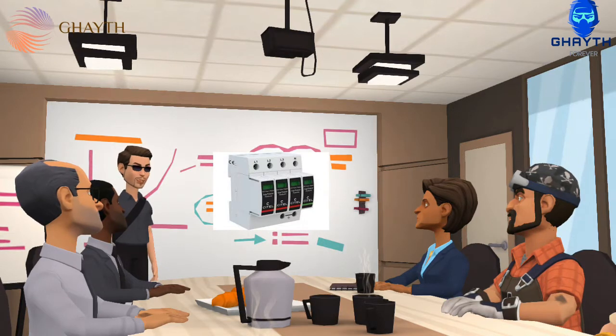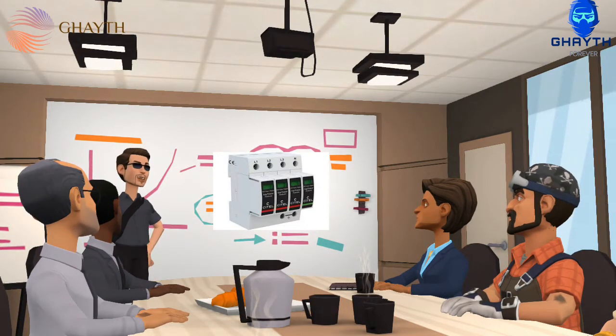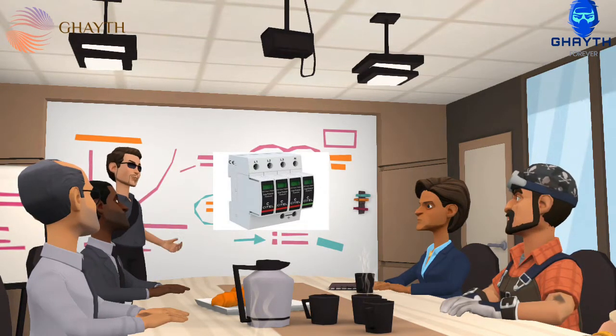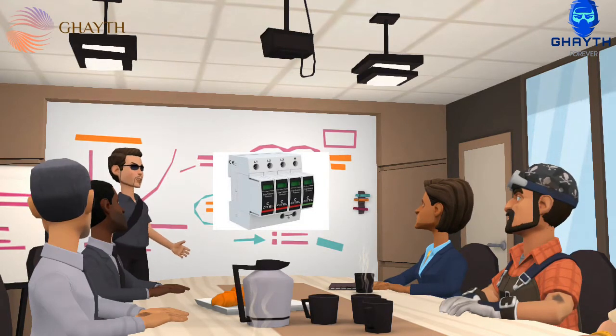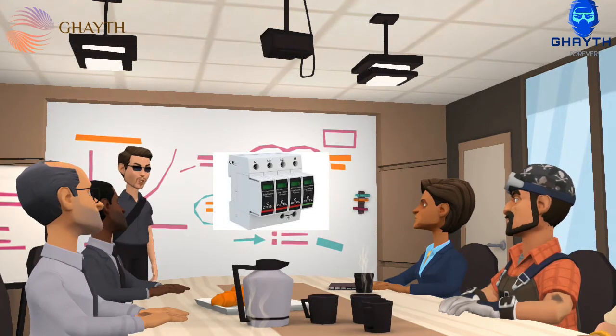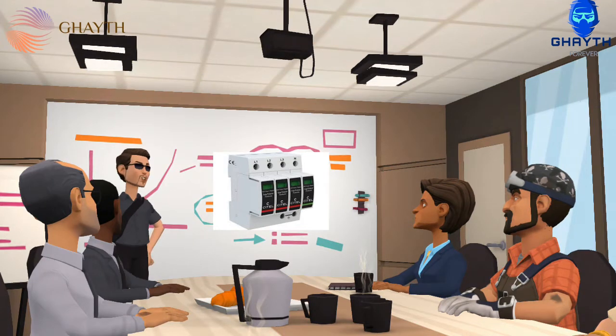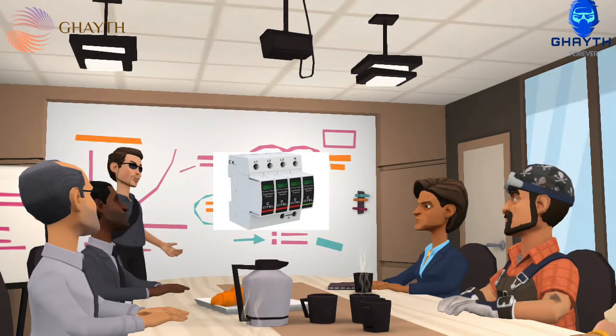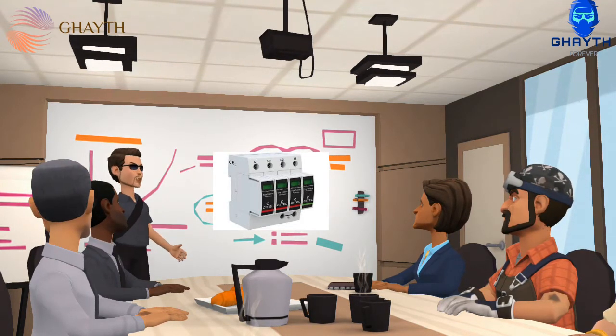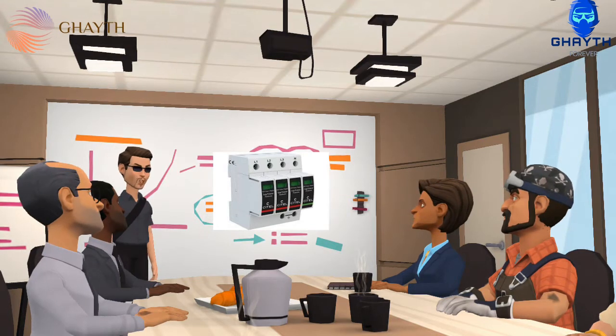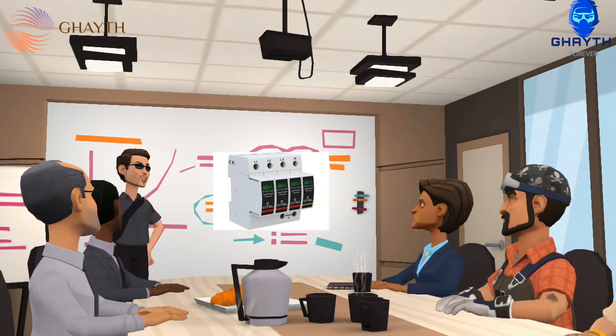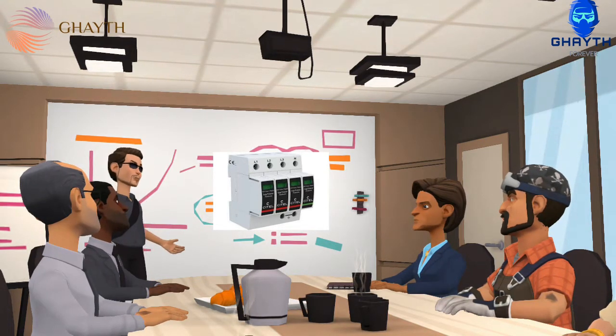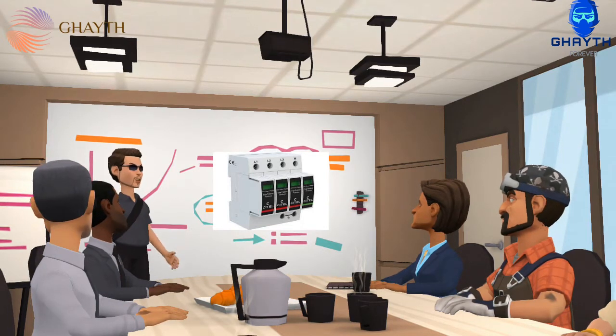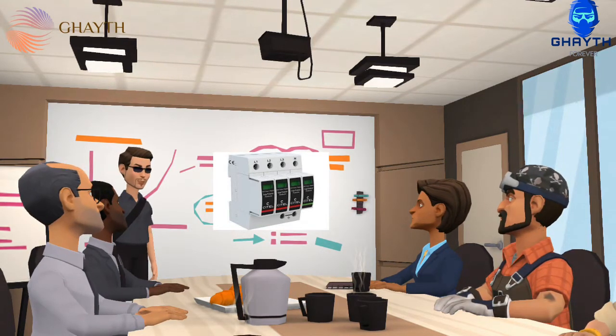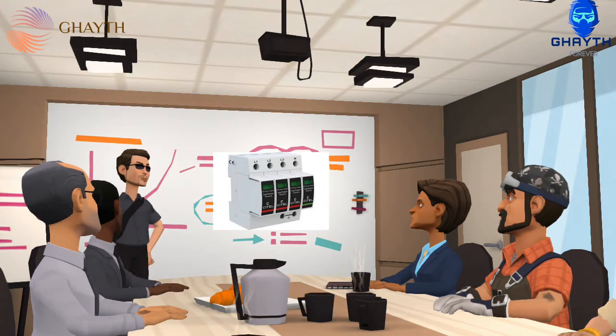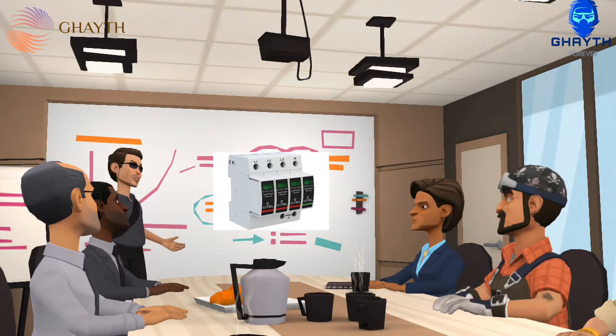The voltage is reduced as the shorting current flows through the resistance in the power lines. The spike's energy is dissipated in the power lines and/or the ground, or in the body of the MOV, converted to heat. Since a spike lasts only tens of microseconds, the temperature rise is minimal. However, if the spike is large enough or long enough, like a nearby hit by lightning, there might not be enough power line or ground resistance, and the MOV, or other protection element, can be destroyed and power lines melted.